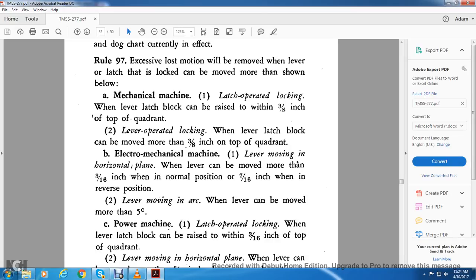B. The electromechanical machine. 1. The lever moving in the horizontal plane, when the lever can be moved more than 3/16 of an inch in normal position, 7/16 of an inch in its reverse position. 2. The lever moving in an arc, when the lever can be moved more than 5 degrees.